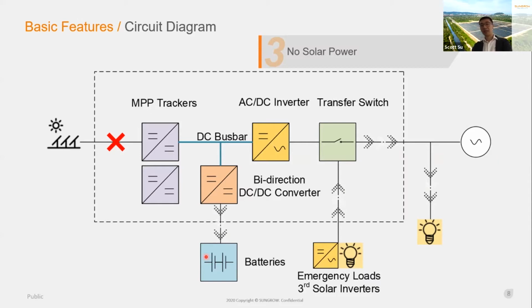Another scenario is very similar. This one is very common in retrofitting systems. When the new Sungrow hybrid inverters don't install the new PV arrays, the system can still work, and the system can still use the existing solar system power to charge the batteries.